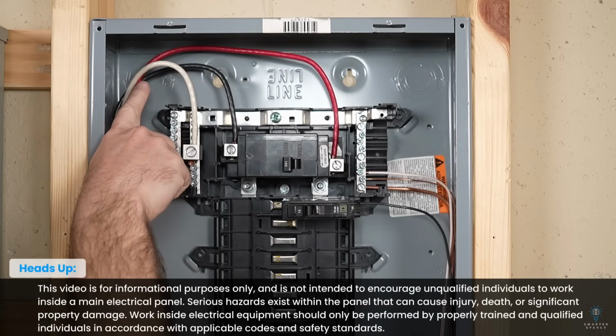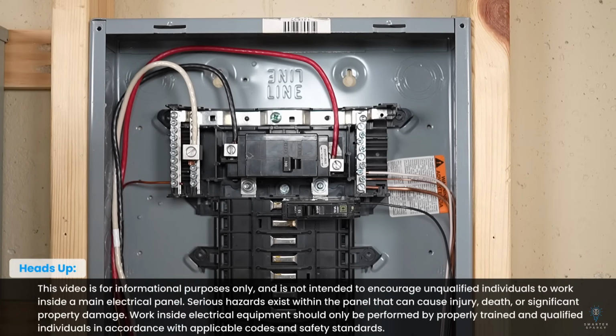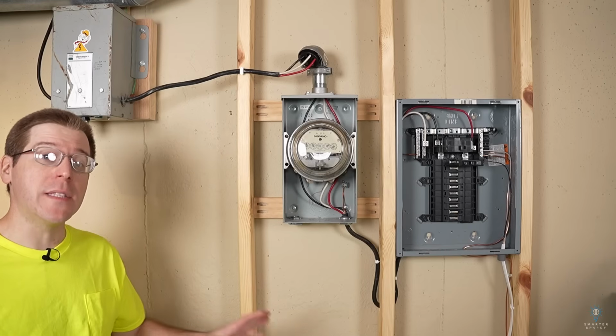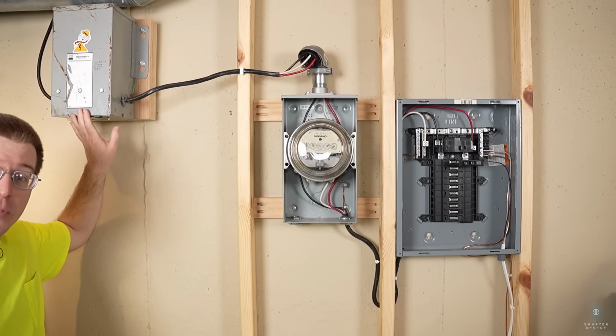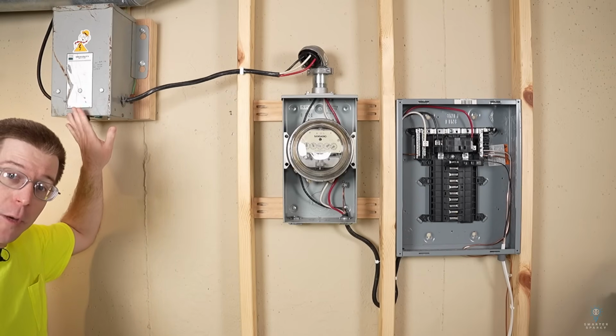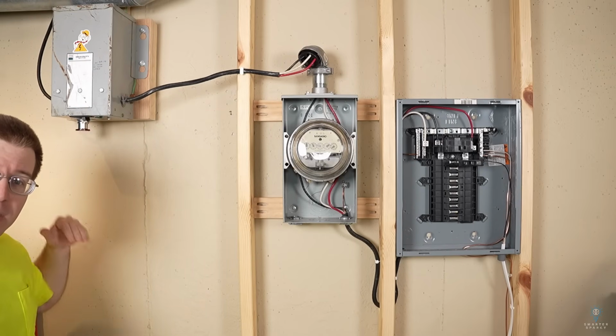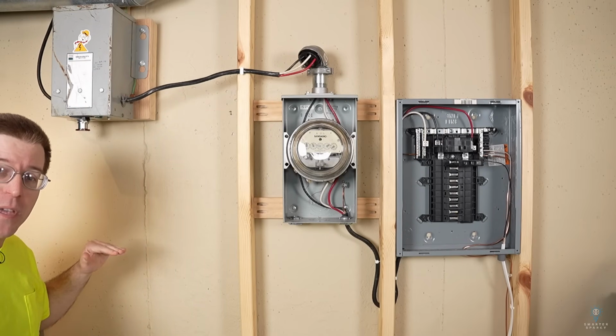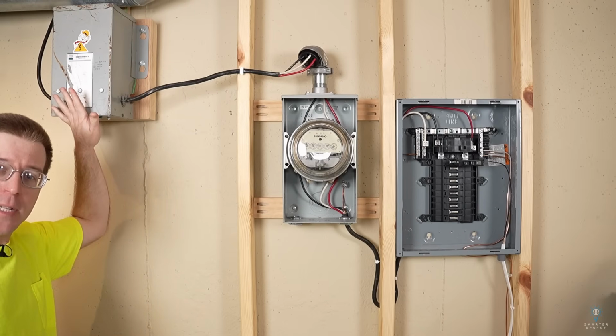These are the service entrance conductors, and in order to understand where they go in the panel, we need to understand where they come from. So let's zoom out and take a look at the big picture. This represents the utility transformer. It could be mounted up in the air, or it could be mounted on the ground in a pad-mounted configuration. Here I've got it as if it was mounted up on a pole.